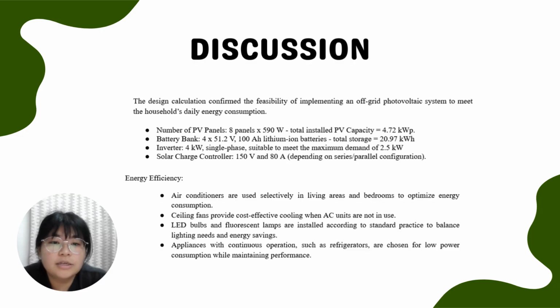X.3 years. So the design calculation confirms the feasibility of implementing an off-grid photovoltaic system to meet the household daily energy consumption. So the number of PV panels which we use is 8 panels with 590 watts, so the total installed PV capacity is 4.72 kilowatt peak. So for the battery bank, we use 4 battery banks with 51.2 volt. So the total storage is 20.97 kilowatt hour.